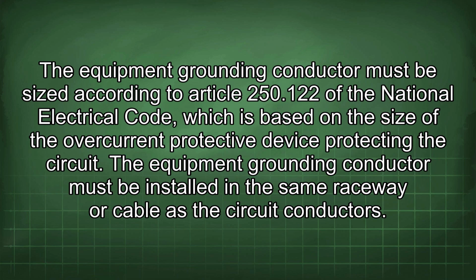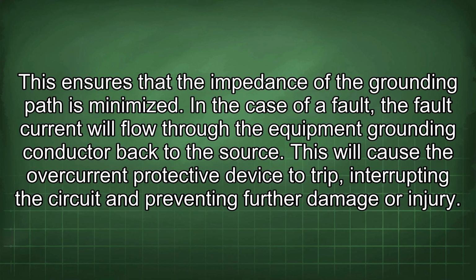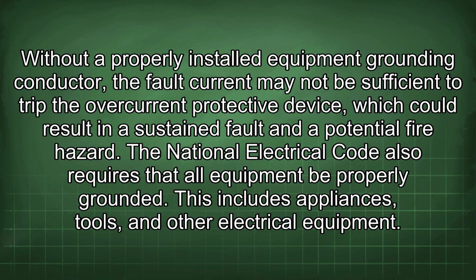The equipment grounding conductor must be installed in the same raceway or cable as the circuit conductors. This ensures that the impedance of the grounding path is minimized. In the case of a fault, the fault current will flow through the equipment grounding conductor back to the source. This will cause the overcurrent protective device to trip, interrupting the circuit and preventing further damage or injury. Without a properly installed equipment grounding conductor, the fault current may not be sufficient to trip the overcurrent protective device, which could result in a sustained fault and a potential fire hazard.